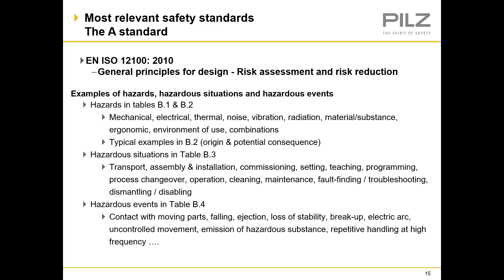Hazardous events include contact with moving parts such as falling, ejection, loss of stability, and breakup — for example, if filling a glass bottle and the pressure isn't controlled, you could shatter the bottle causing glass and shrapnel. There are also electric arc, uncontrolled movements, emissions, and repetitive handling at high frequency. EN 12100 is a requirement to conduct a risk assessment of this type on all equipment, whether for the OEM or the end user.